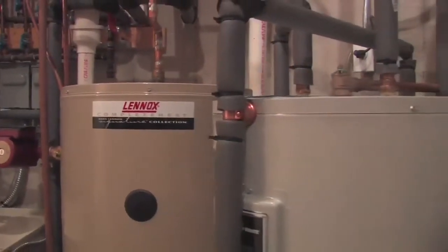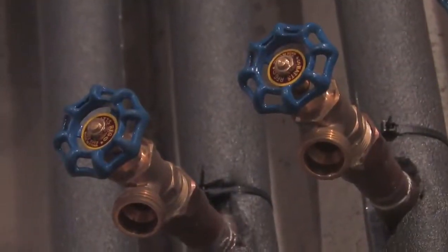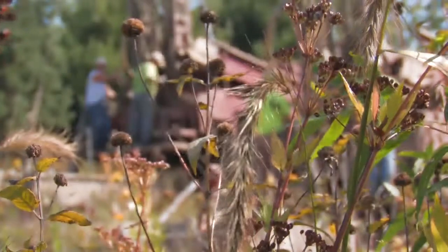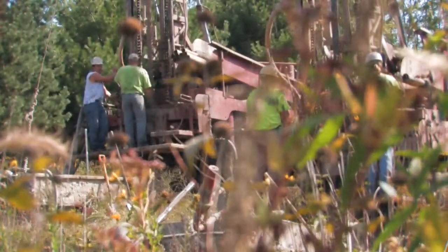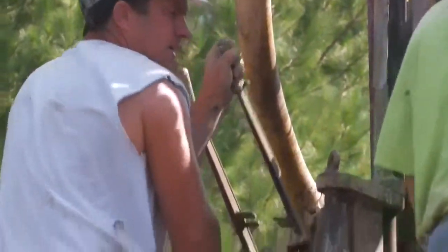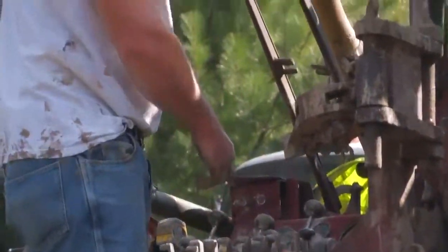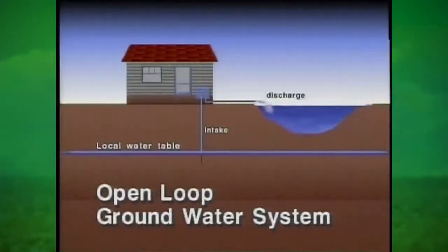We use piping many times. We'll do vertical drilling where we'll set up a drill rig, drill a number of holes in that property, and send piping down into the ground. We transfer heat through a solution of water and antifreeze from the earth to the heat pump. That would be what we call a closed loop vertical system. There's an open loop system where we can use an existing potable well, or drill another well with a pump in it, send that water into the heat pump, and then discharge that water where it returns right back into the aquifer.